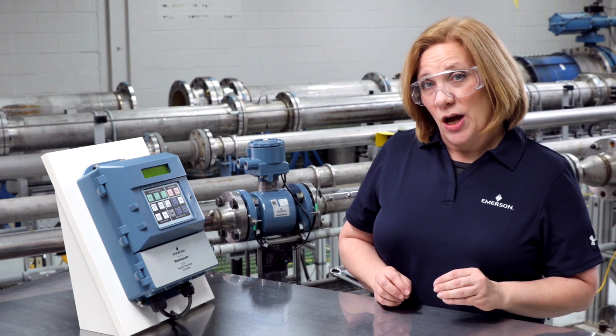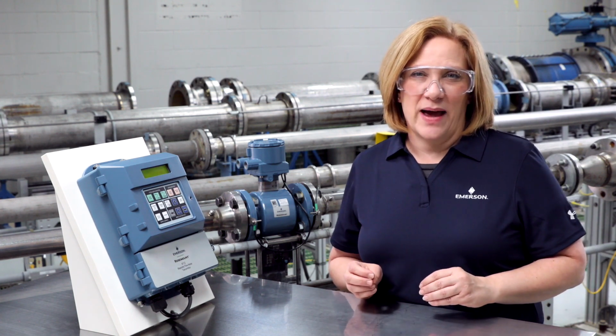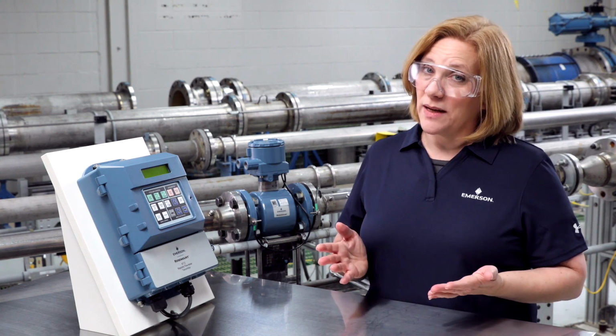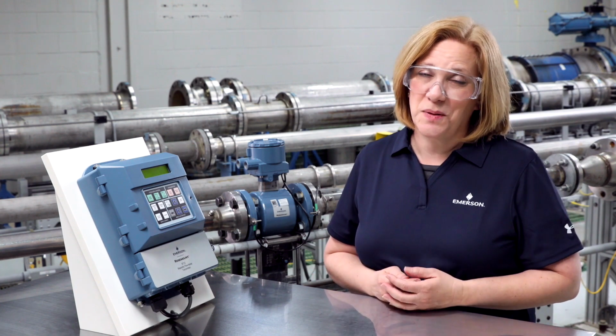There are two limits that need to be set, electrode coating limit 1 and electrode coating limit 2. The default values for this are 1,000 kiloohm and 2,000 kiloohm respectively. However, these should be customized for each application to be the most effective. When limit 1 is reached, it indicates that coating is starting to occur, and when limit 2 is reached, it indicates that flow measurement is compromised and the meter should be cleaned immediately.